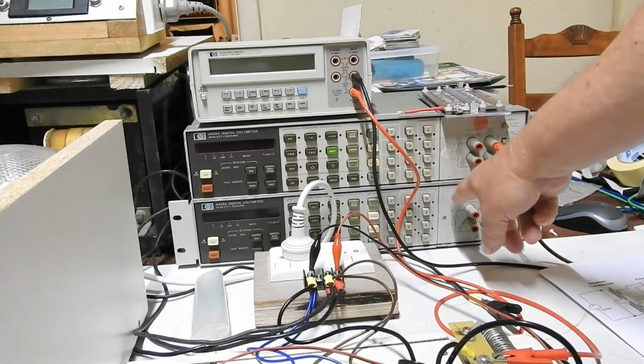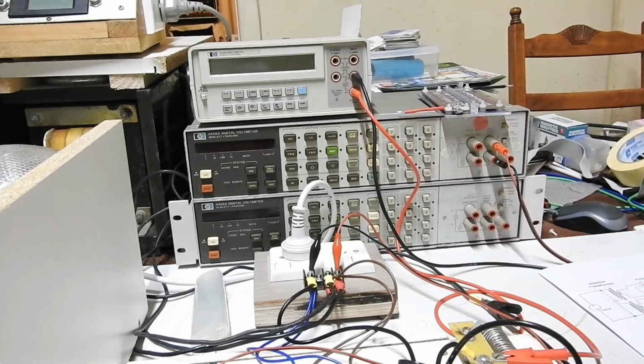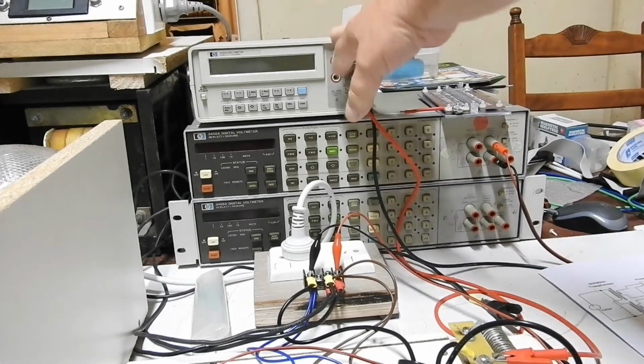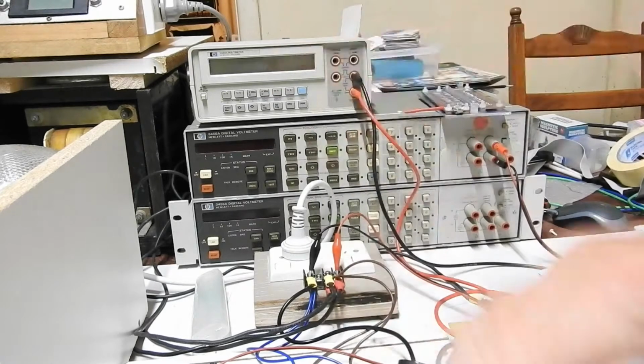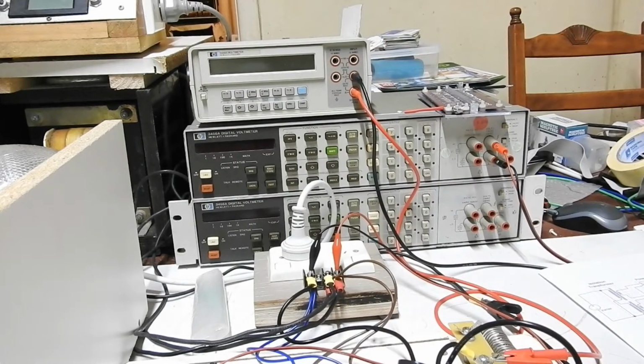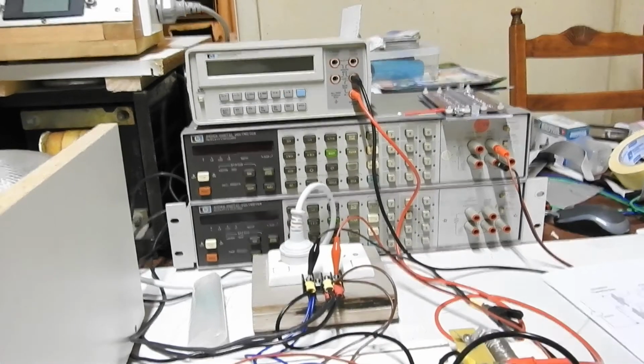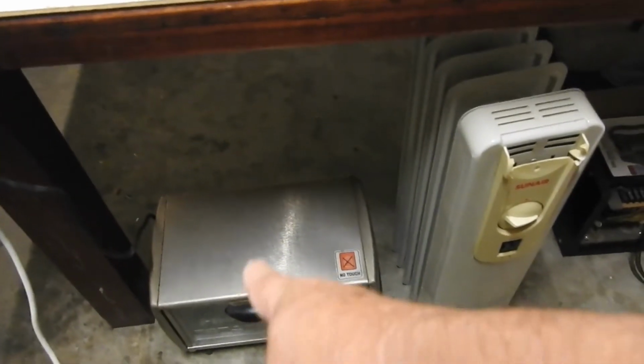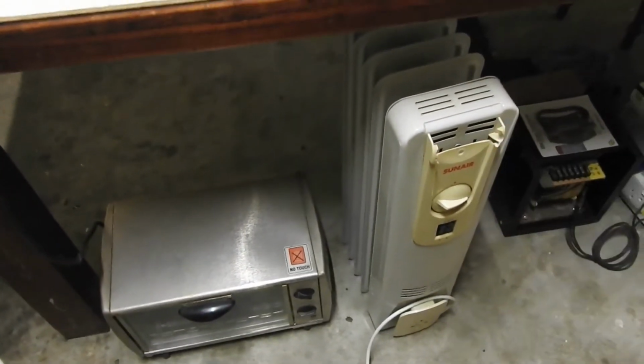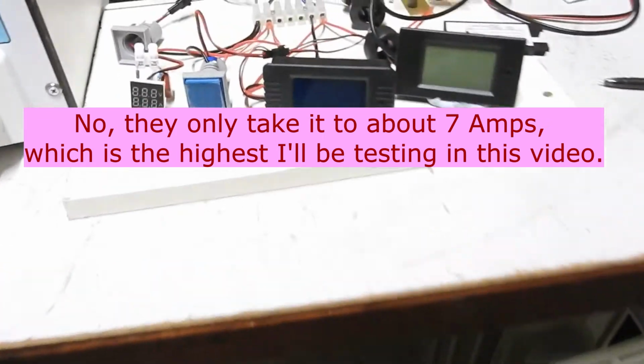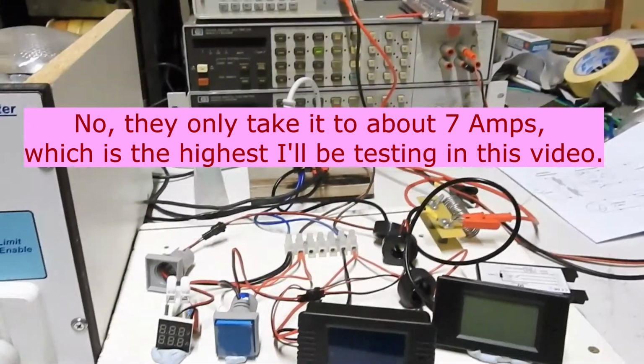These bigger HP meters can't do current. Even so, this one is only good for 3 amps, and I want to test this stuff up to about 10 or even 20 amps by putting on loads like that toaster oven and this oil-filled heater contraption, and I can get up to about 20 amps of load that way.